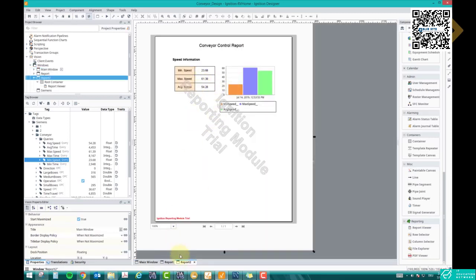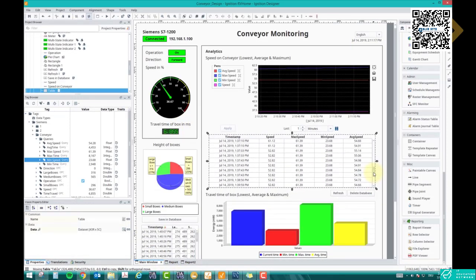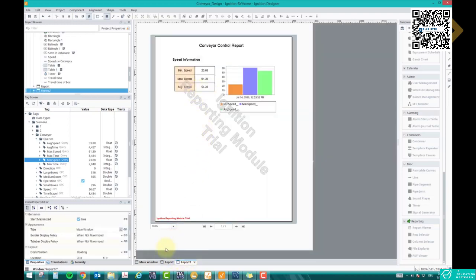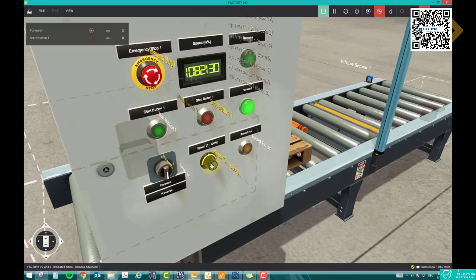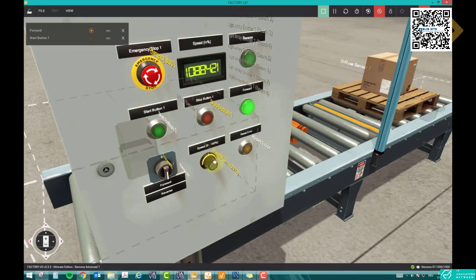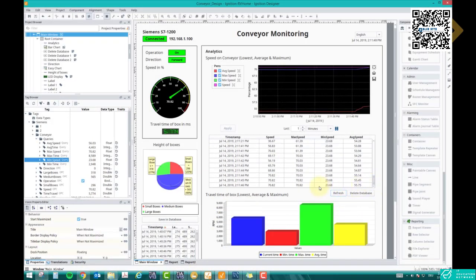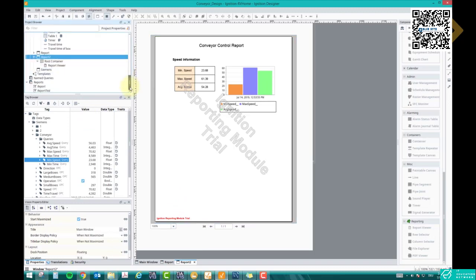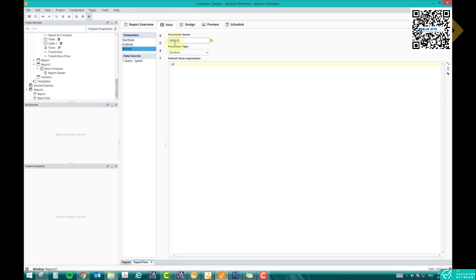The average is 54.28 in the live data and the same in the report. Minimum is 23.68 — same here. Maximum is 61.39. Now let me change some values by increasing the maximum, then refresh. Maximum is now 70.84, but in the report it still shows the old value. This is what I'm trying to explain — we need to refresh these values. If you remember, we created a parameter named 'refresh' with Boolean type and default value zero. In Ignition SCADA, whenever you change any parameter, it refreshes the report — that's the trick.